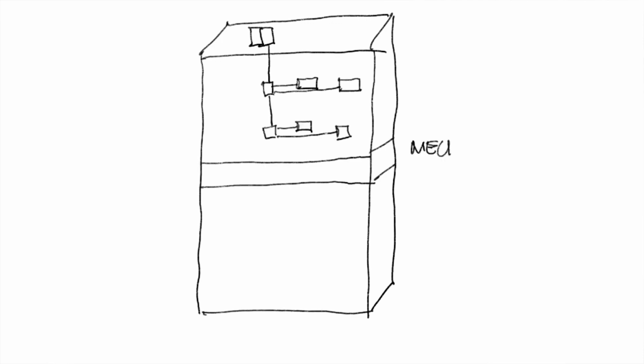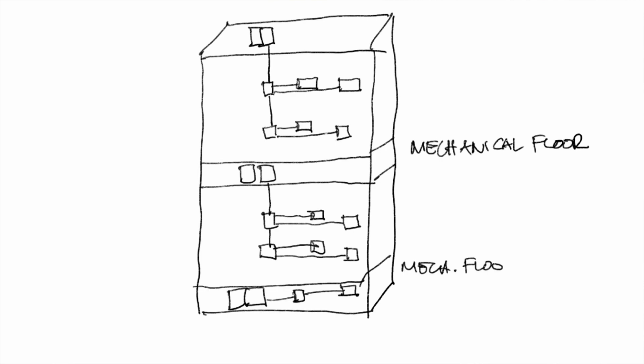So how do we address multi-level buildings where the total height of the building is above the vertical limitation of the equipment? The easiest way to do this is to space out the VRF systems throughout the height of the building. So typically what we'll do in this type of application is we'll have a number of VRF systems up on the roof, and then we'll pipe down to however far down we can go. And then we'll have, say, a mechanical floor. Well, we'll put more VRF systems there, go down another number of floors, another set of VRF systems on another mechanical floor, and so on and so forth. So that's the easiest way to address a multi-level building, office building, or a tall residential tower.